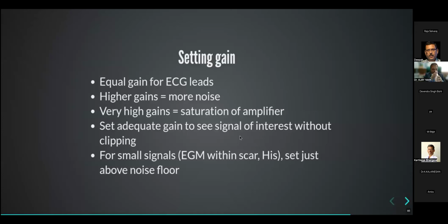And when you have small signals, this becomes important when you're doing SCAR-VT mapping, etc. So what is the gain that you should set? So there's no magic number. The best way is to keep gaining it up till you see noise, and then just gain it down one step. That way you see that anything that is above noise you will see, because I think the general principle in a pathologic heart is any signal that is higher than noise can be important, and you should be able to see it. So for that, you should make sure that your gain is sufficient that you will just see noise.